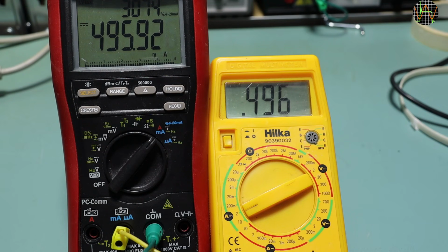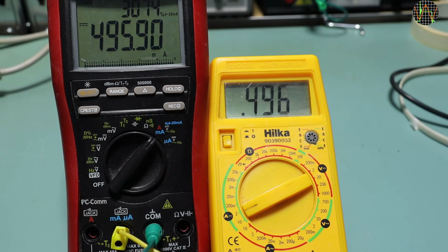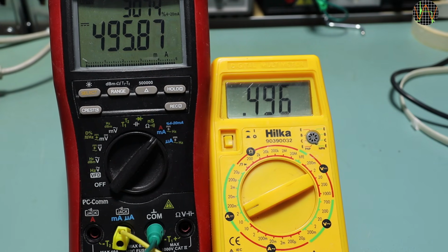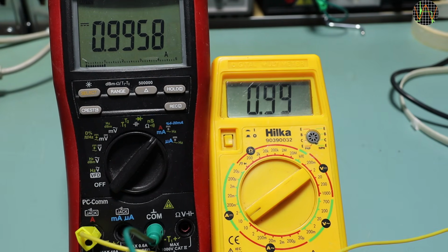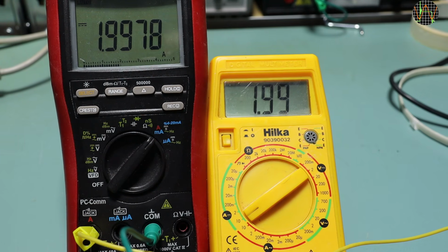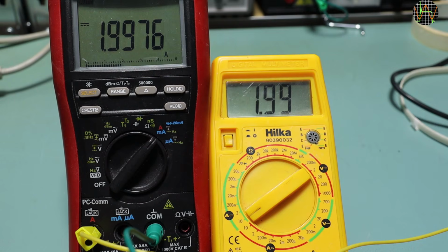Switching to the 2 amp range on the Hilka, 500 milliamps is spot on. Switching to the 10 amp range on the Brymen, 1 amp and the meters are close. Switching to the 10 amp range on the Hilka, 2 amps and the meters read practically identical. Same for 5 amps and 9 amps. I think the Hilka works very well in DC amps, no need for any calibration.